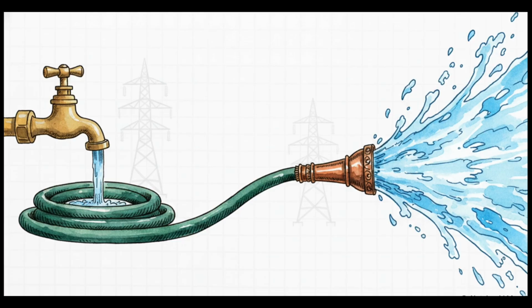When a medium or long transmission line is basically empty, meaning it's operating under no load or really lightly loaded conditions, sending electricity down the wire actually makes the voltage increase at the destination. How on earth is that possible?